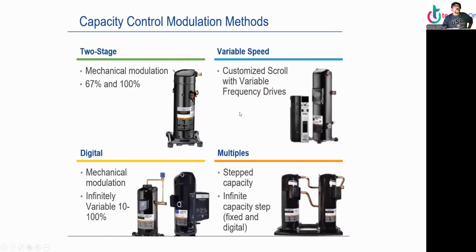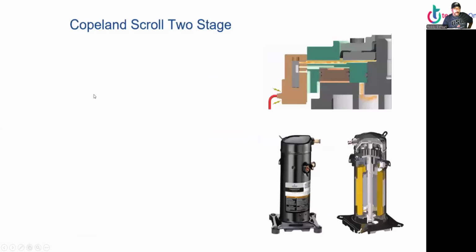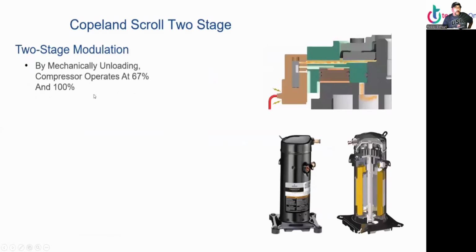So the scroll capacity control modulation methods. We have two-stage modulation, 2/3 capacity and 100%. Customized scroll with variable frequency drive. Mechanical modulation. Stepped capacity, infinite capacity. I'm just going to cover the first one. Two-stage scroll modulation is by mechanically unloading a compressor; it operates at 2/3 capacity or 100% capacity.